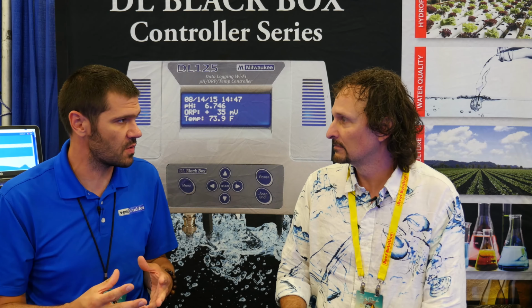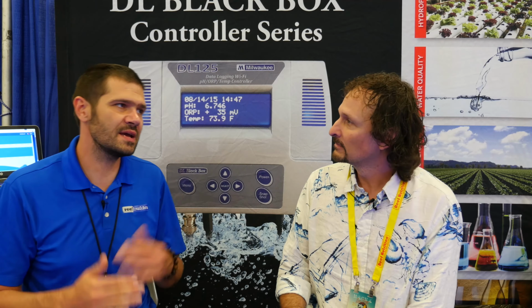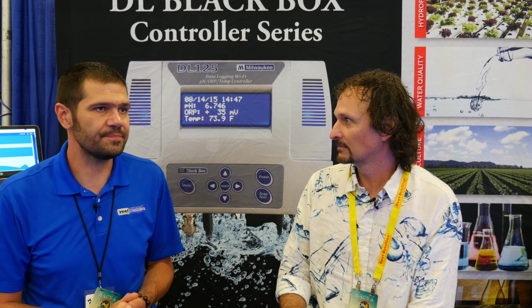After the temperature of your water and the salinity of your water, the pH of your water is one of the other parameters that governs all of the reactions that are going on within your aquarium. And we really take it for granted how much this is overseeing the rate of reactions inside of aquariums. You know, people say, oh yeah, I need a pH between 8 and 8.2, 8.2, 8.4. But if you're off by 0.2, you might be way outside that scale. And a high pH leads to high coral growth. So having a really critical and reliable pH measurement device, a pH controlling device, is one of those things that can really, really drive your coral growth in your aquarium. Oh, increase the health of the entire ecosystem.